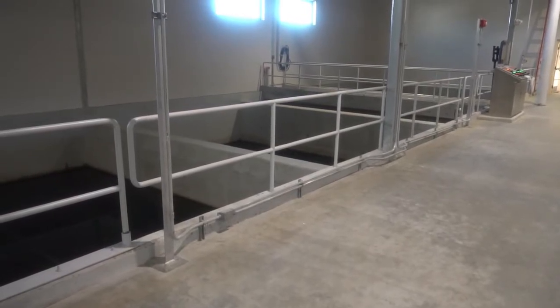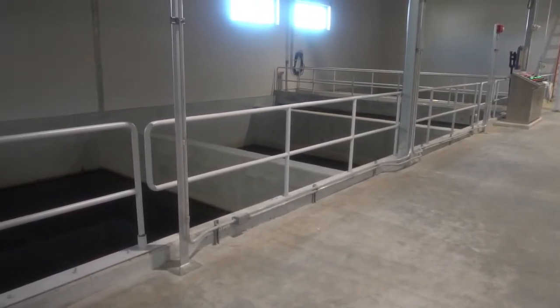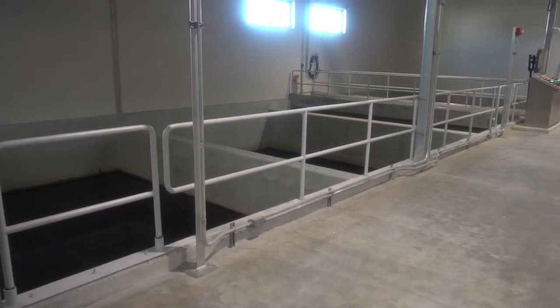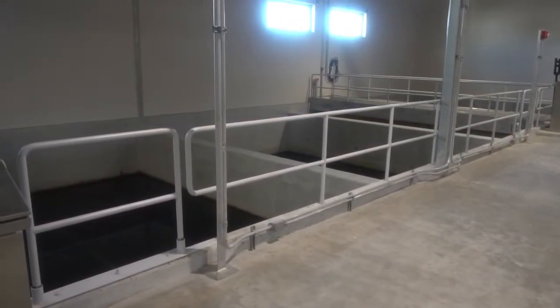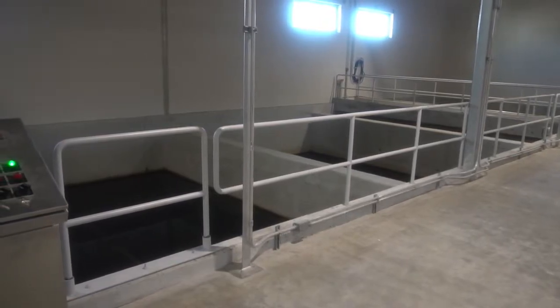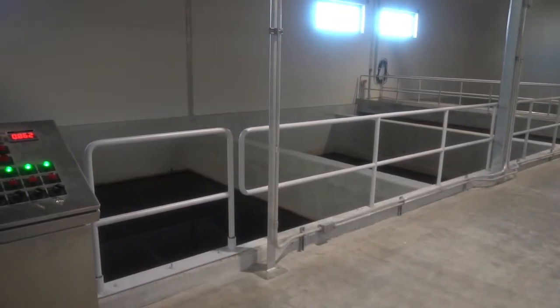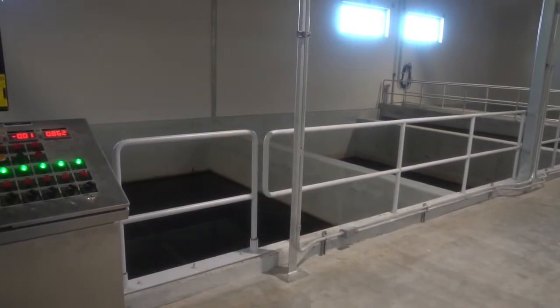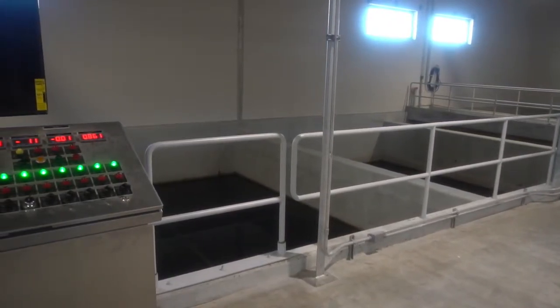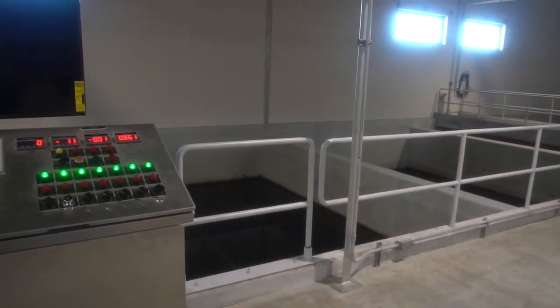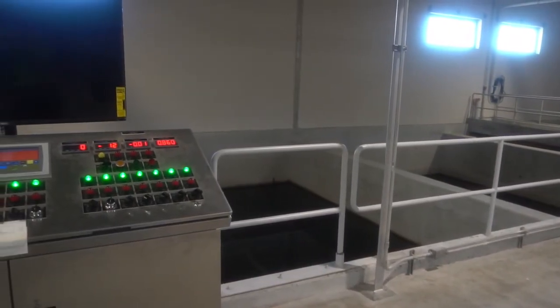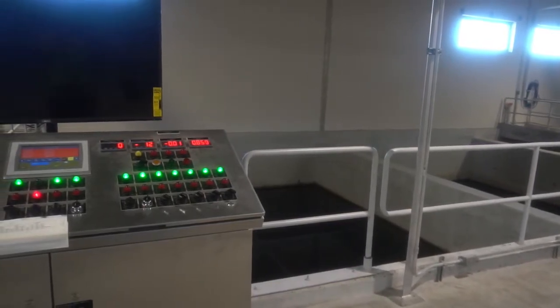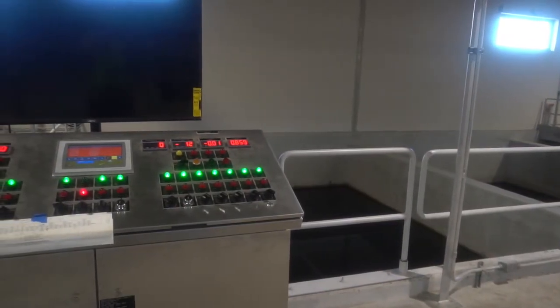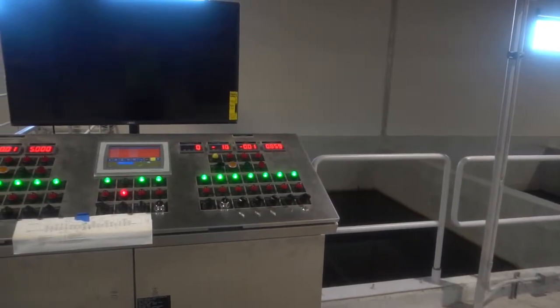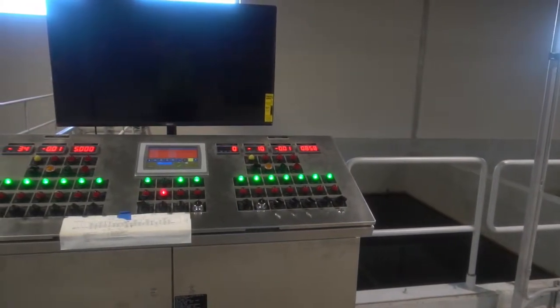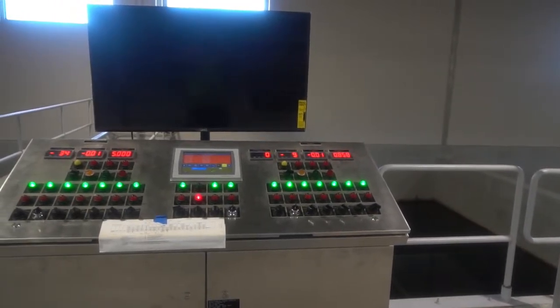Here there are 4 filter units. Each is capable of a nominal rate of 4 million gallons a day. The filters have a freeboard of 4 feet of water above and 3 feet of specifically graded granular activated carbon and a half-foot layer of sand at the base. Pilot studies and scientific tests of these granular activated carbon units aided in design and choice of media. The filters utilize a scientific process of adsorption, which is different than simple mechanical filtration.